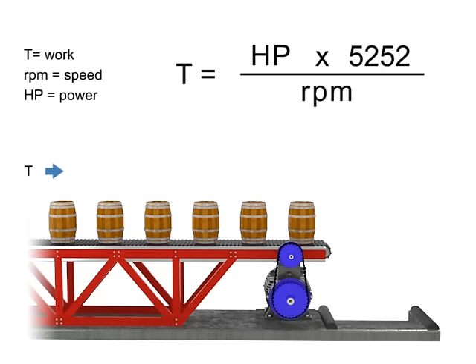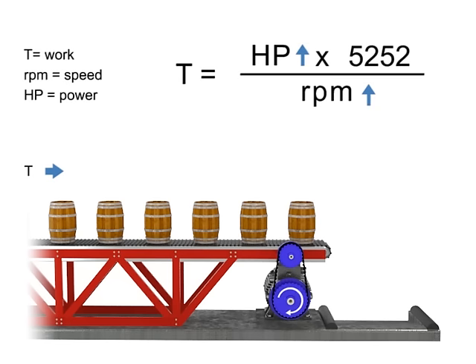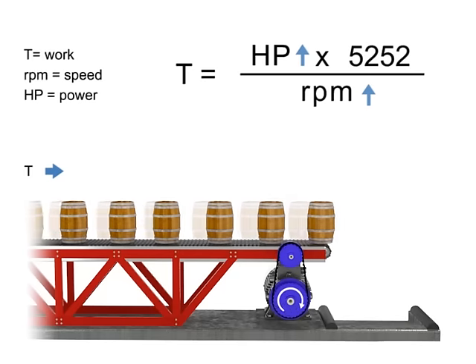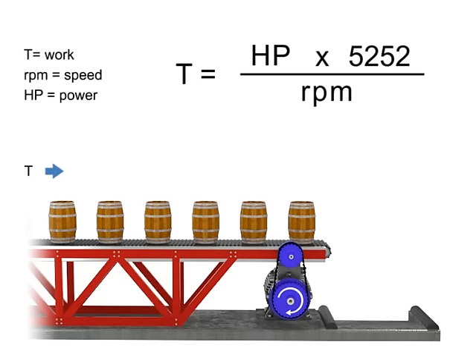Let's say we wish to keep torque constant but want to increase the production of barrels. If the torque, or number of barrels, on the conveyor belt remains constant but speed increases, then the horsepower of the motor also increases. In other words, a more powerful motor is required to produce the same amount of torque more quickly. Similarly, the opposite is true: if we wish torque to remain constant and decrease speed, then the horsepower of the motor also decreases.